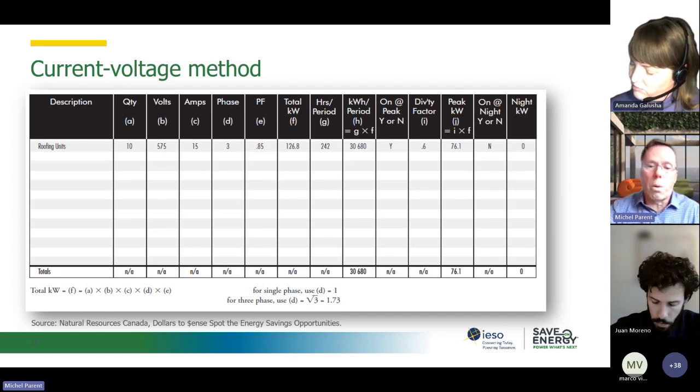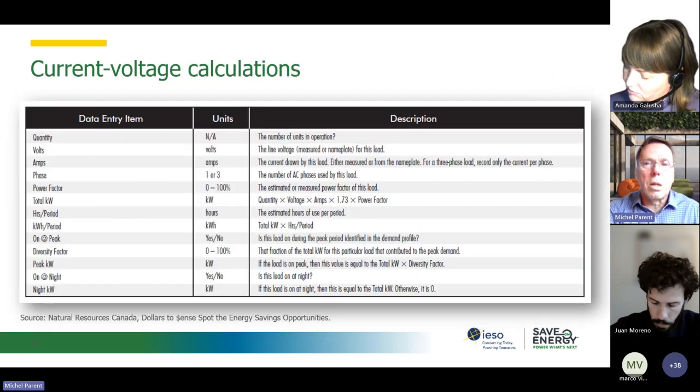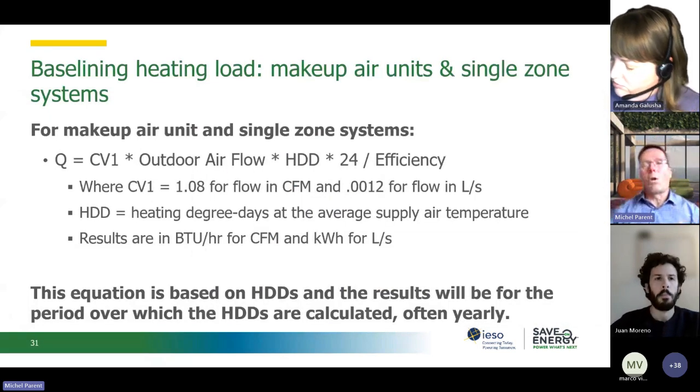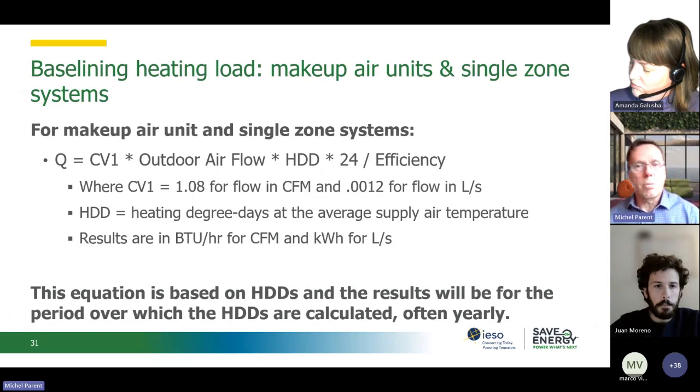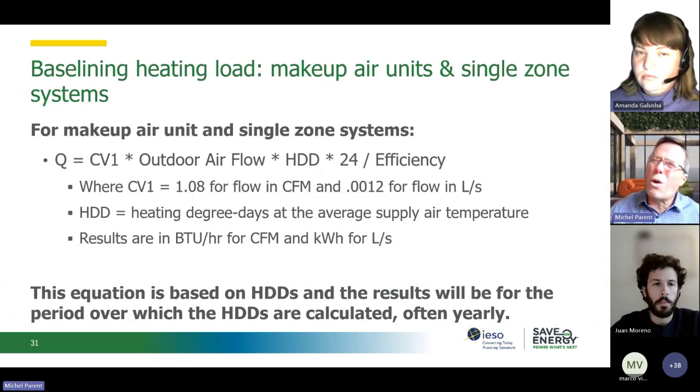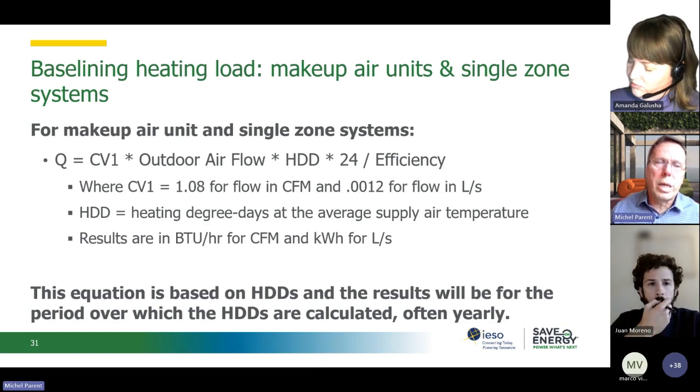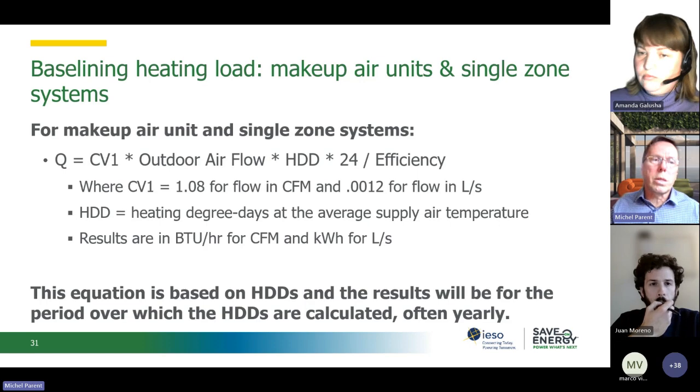Now, for the thermal equipment, you would have to do something similar, but usually I don't use the boiler size times the number of hours. If you do a very, very rough estimate, you could always do that, but it's usually quite inaccurate. You're better to look at your load. So let's talk about the ventilation load.